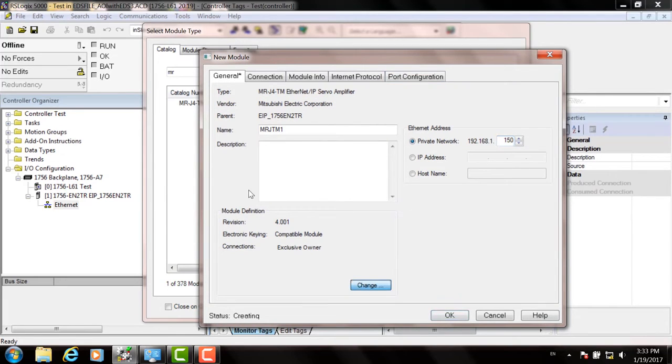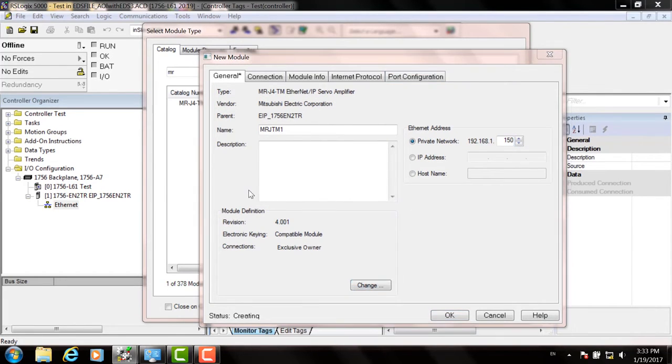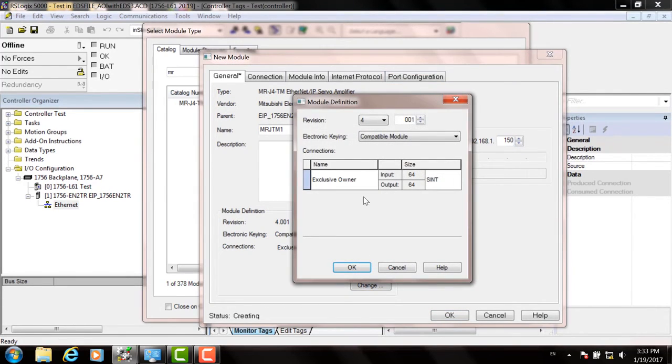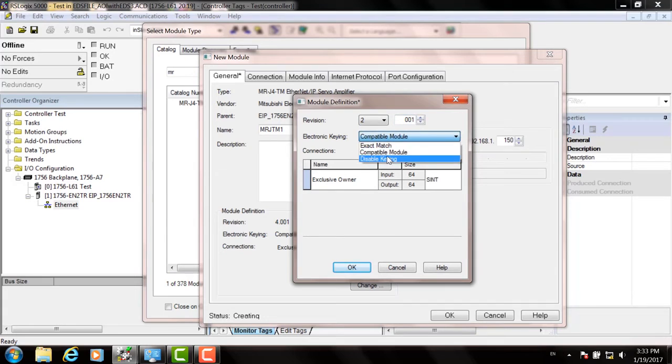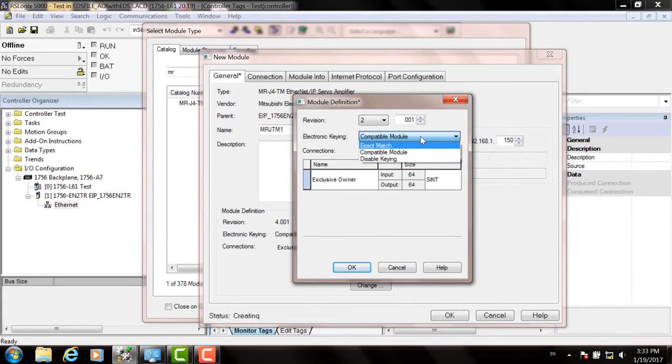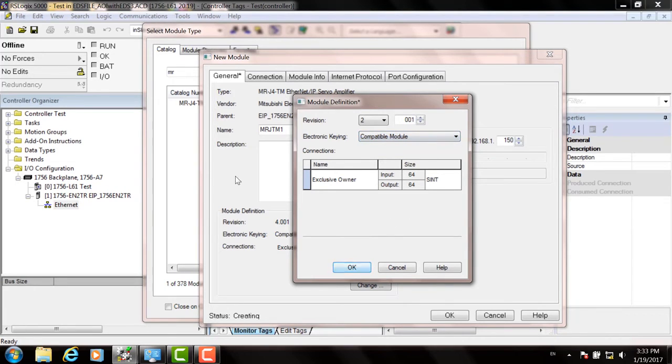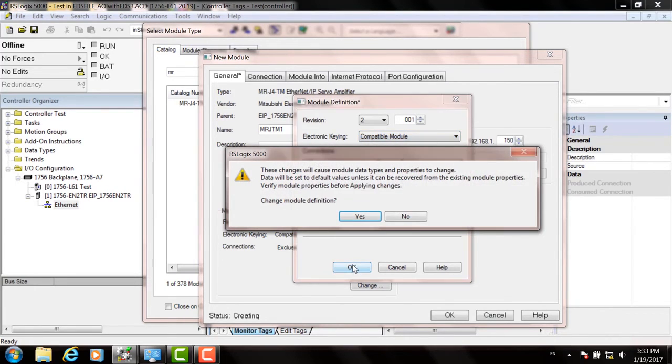Next, click the Change icon down at the bottom. And you can either set the revision to match what was shown in the IP config utility, or in this pulldown you can choose Disable Keying. And I recommend that because now you don't have to look at the revision number for each drive.